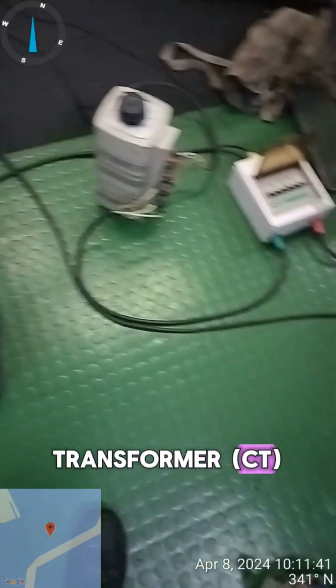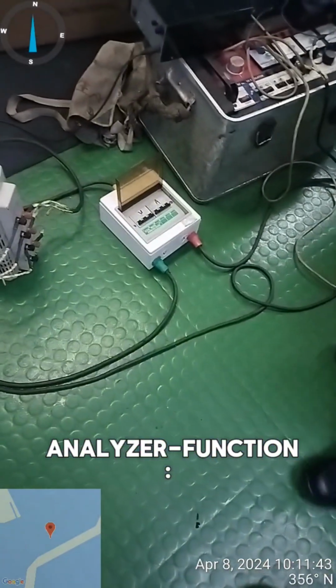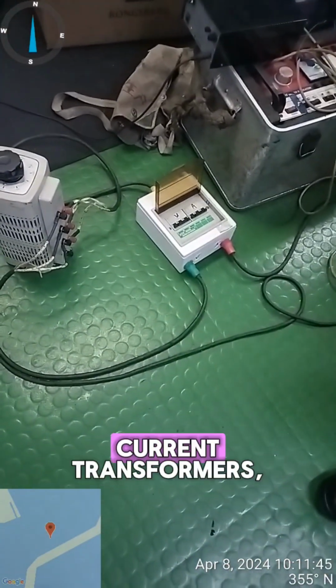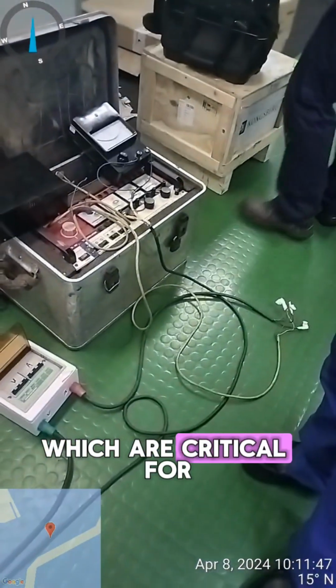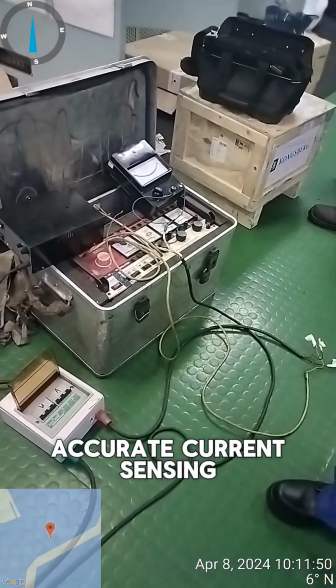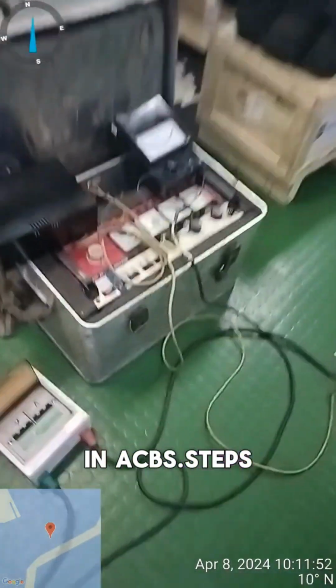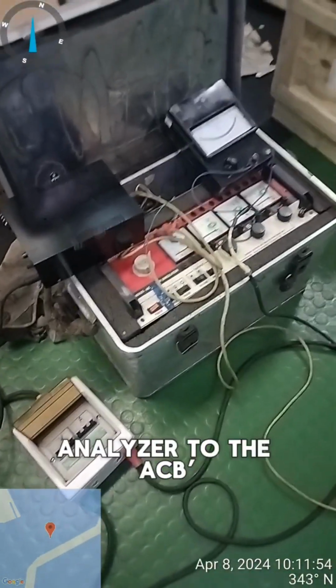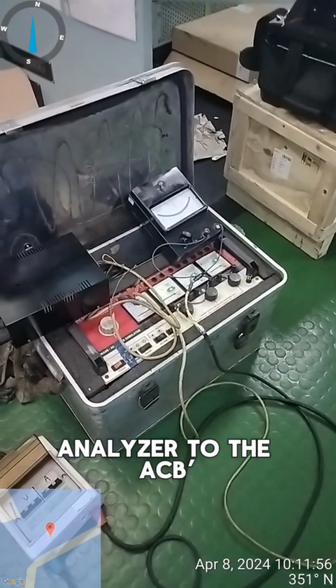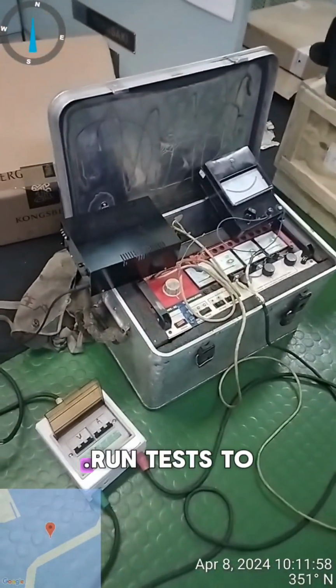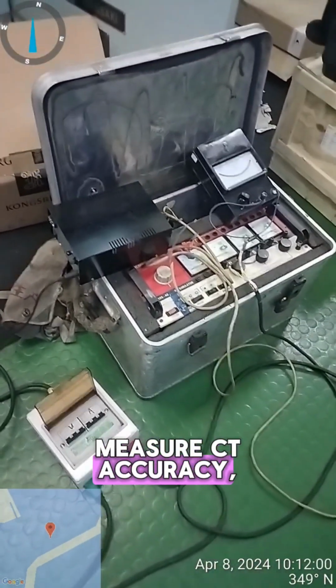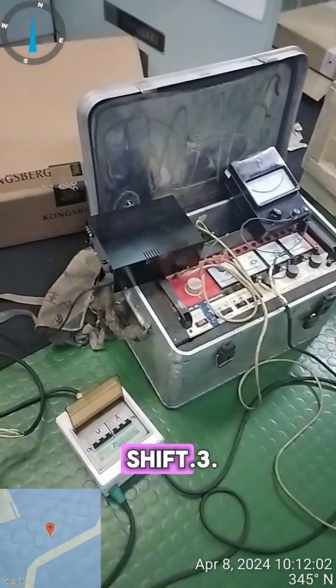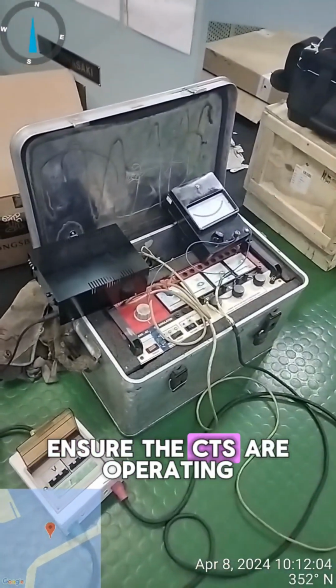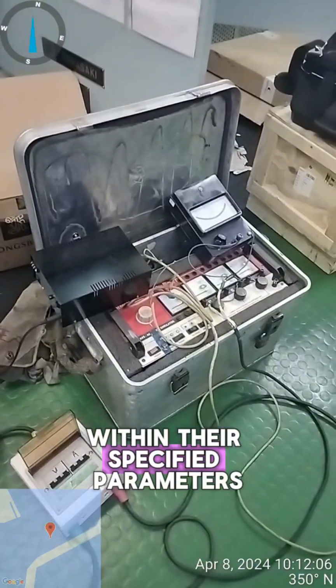5. Current transformer (CT) analyzer. Function: verifies the performance of current transformers, which are critical for accurate current sensing in ACBs. Steps: 1. Connect the CT analyzer to the ACB current transformers. 2. Run tests to measure CT accuracy, ratio, and phase shift. 3. Ensure the CTs are operating within their specified parameters.